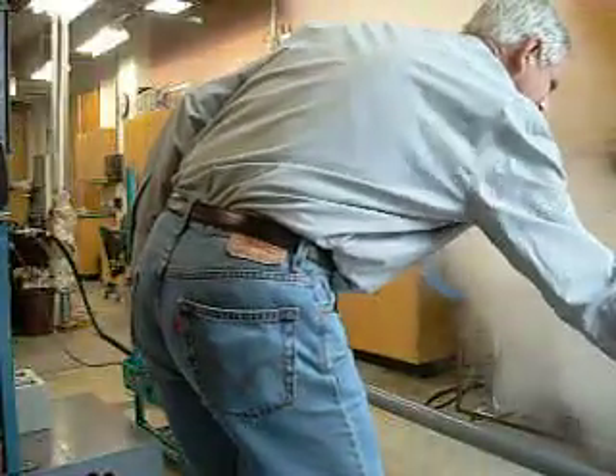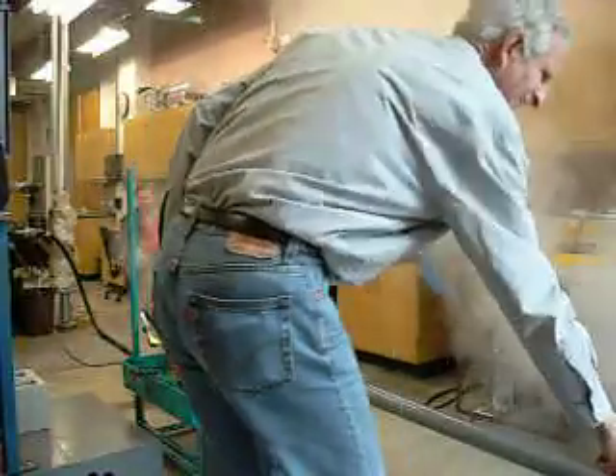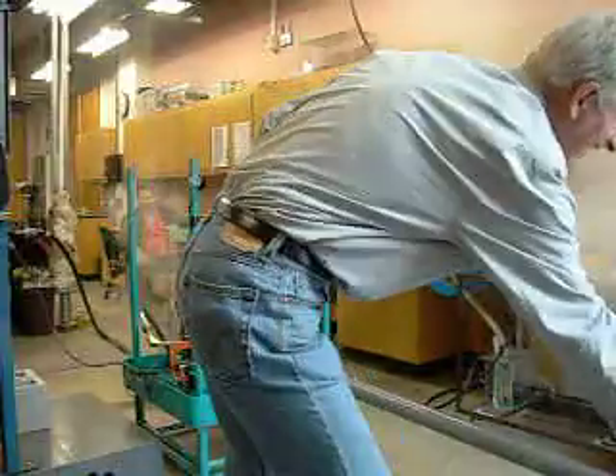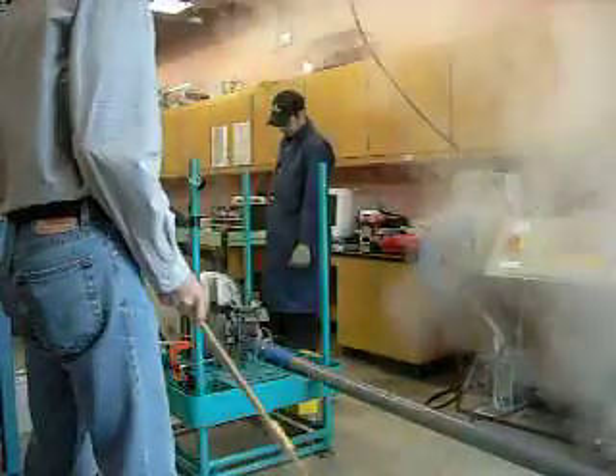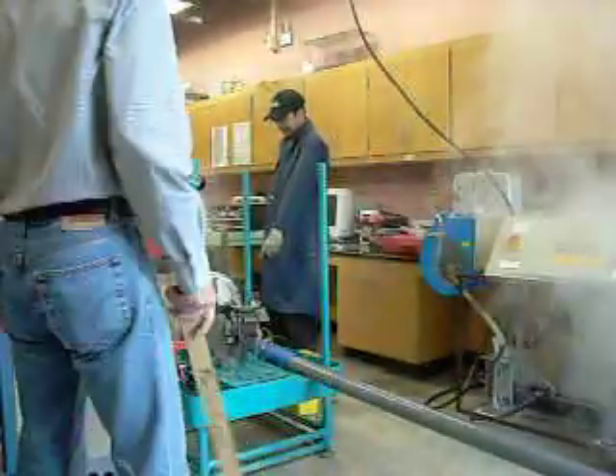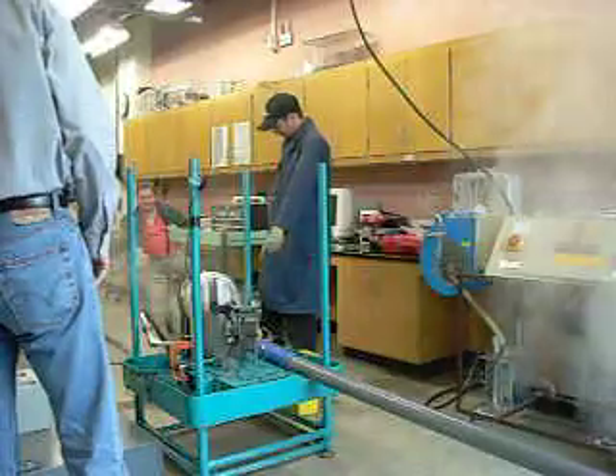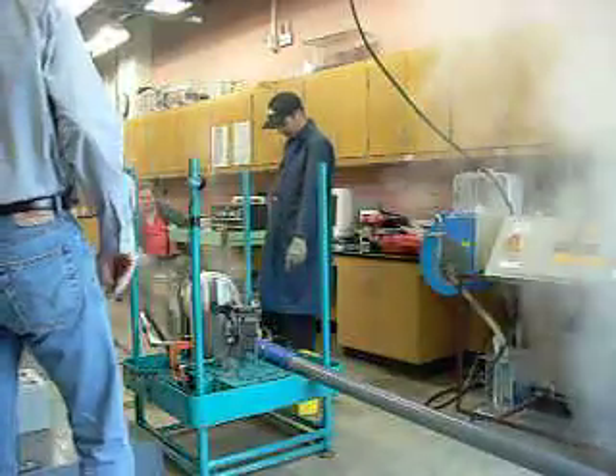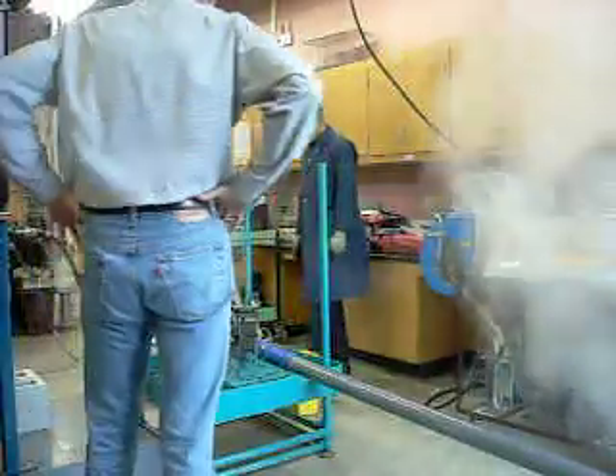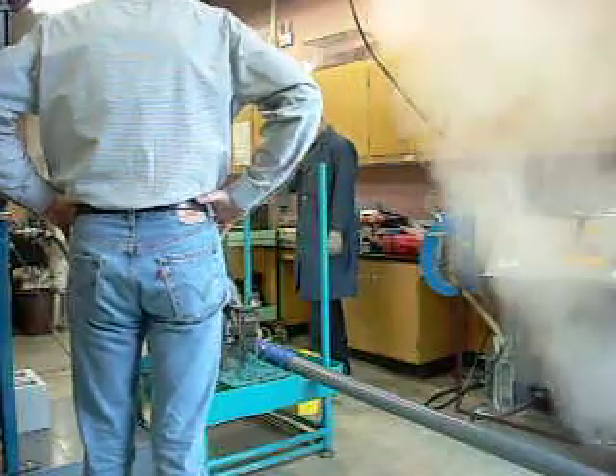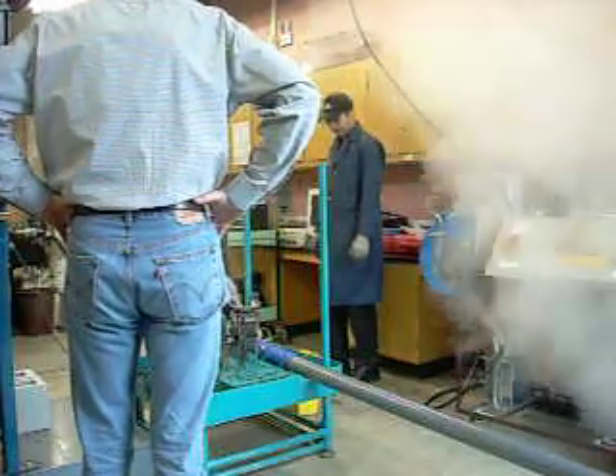You just let that run outside. What's our exhaust pressure? Nothing? So it's 95 at the gauge, 100 on this gauge. We got pressure there, yeah, that's good. So that's about 5 PSI drop between the two spots.